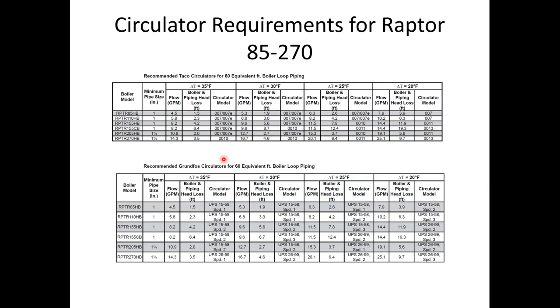The Raptors do not ship with circulators. The circulators are going to need to be sized based upon the delta T that you're looking to run for the boiler. On the wall hung boilers, the 0010 will work for the majority of the products. And again, the circulators are for the near boiler piping. It is in the manual, but it's not recommended to direct connect these products directly to the heating system. If you're going to direct connect them to the heating system, you're going to need to size the circulator to overcome both the pressure drop of the heat exchanger and the pressure drop of the system. So a 007 may not be the circulator to use if you're going to be direct connecting the unit.